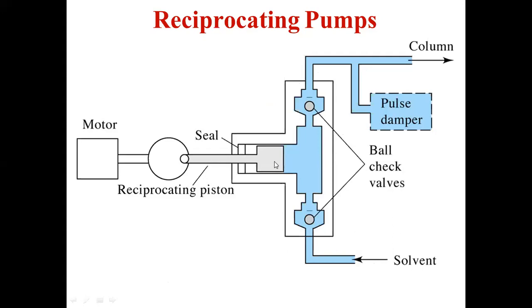You can see a piston here, and this piston is connected to the motor. The motor will always be driving in order to make this piston move. Here the solvent connection will be given from the solvent reservoir, and the other terminal of this reciprocating pump will be connected to the column. When the pressure is created by the movement of the piston, the solvent is going to be sucked from the solvent reservoir, and it will move towards the chamber which is present here, then ultimately towards the column.